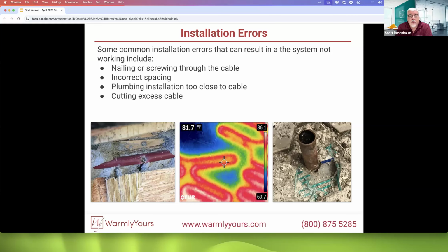That is also a possibility of someone that was doing trim. People putting in trim nails are often putting them in at an angle, and they go down, and sometimes the wire is close and the nail bounces off there and hits the wire. So yes, right there is a perfect example of that.